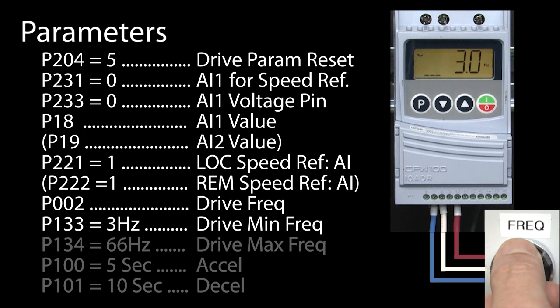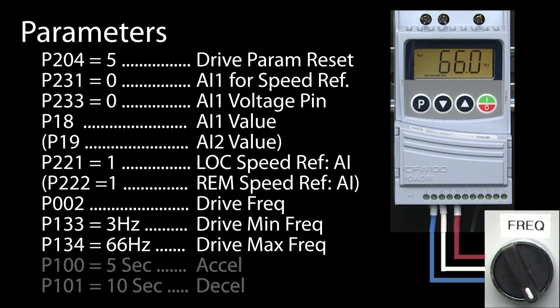If I rotate the potentiometer, sure enough, the drive's frequency changes. If I rotate it all the way clockwise, the drive goes to the max speed, which we can change in parameter 134.